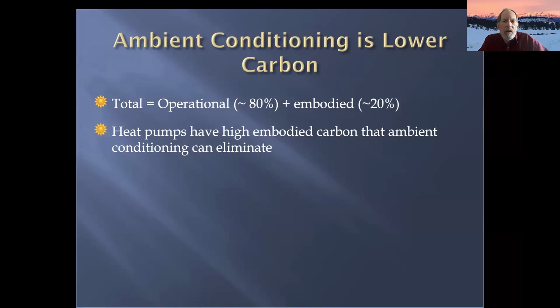Heat pumps have high embodied carbon that ambient conditioning can eliminate, and the signature feature of heat pumps is the refrigerant. R410A, for instance, is 2,000 times worse than CO2 in the atmosphere, and even its replacement, R454B, is 500 times worse than CO2 in the atmosphere.